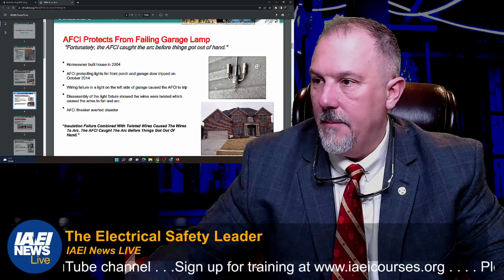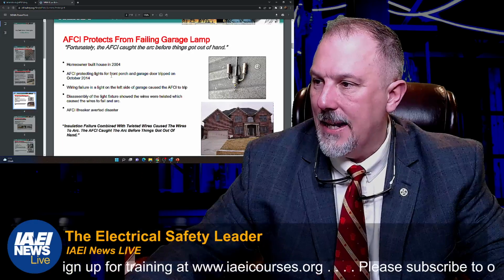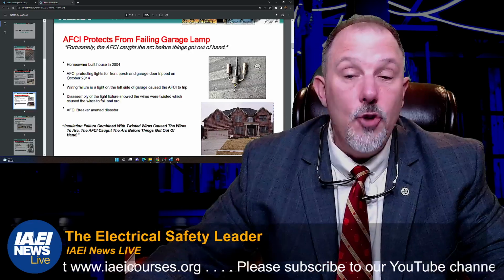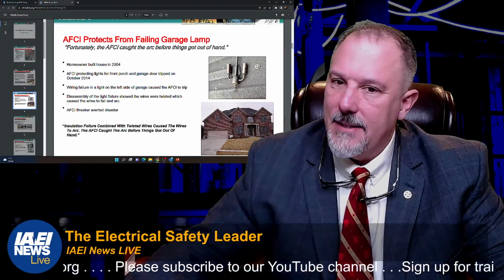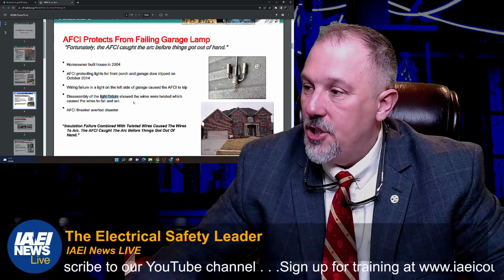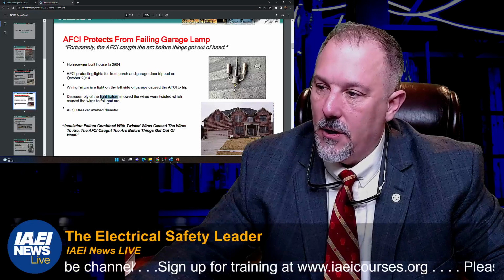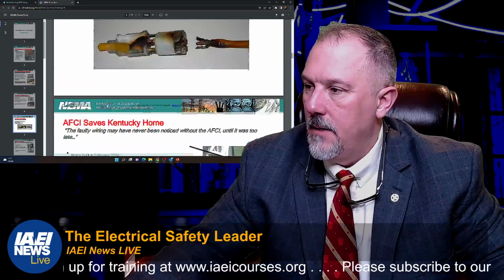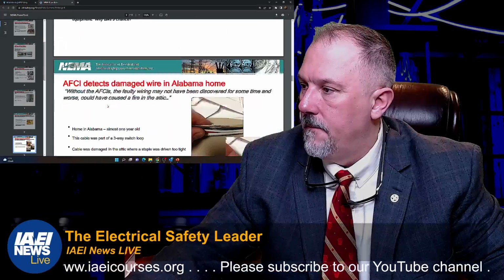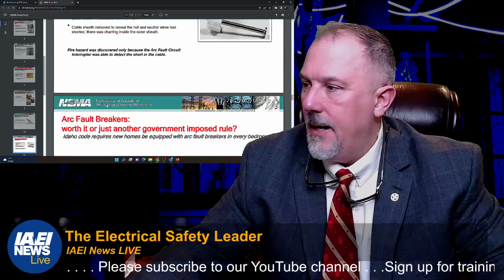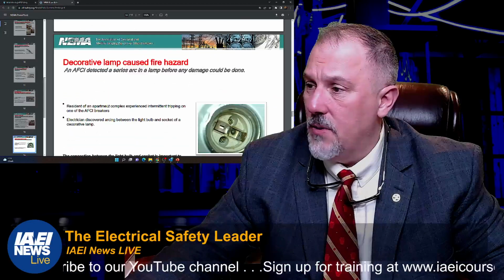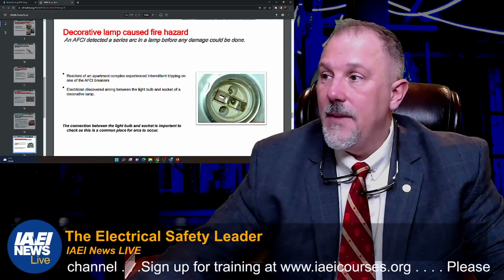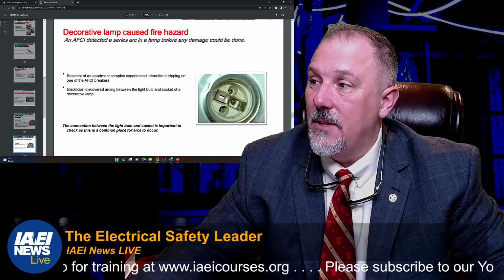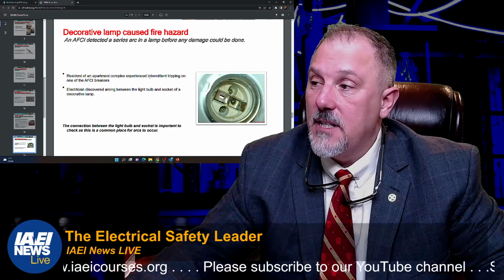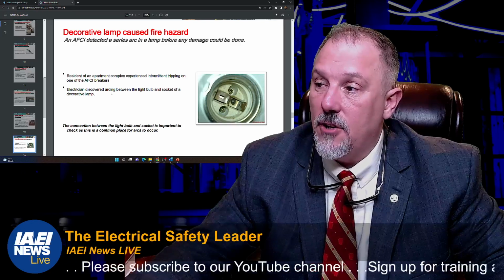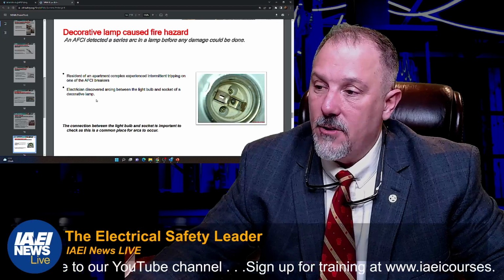Protects from failing garage lamp. Homeowner built house in 2004. AFCI protecting lights for front porch and luminaires. Disassembly of the light fixture, the luminaire, showed the wires were twisted, which caused the wires to fail and arc. AFCI breakers averted disaster. And this is all free and accessible to all of you as well. Look at this: decorative lamp caused fire hazard. An AFCI detected a series arc in a lamp before any damage could be done. A resident of an apartment complex experienced intermittent tripping on one of the AFCI breakers. The electrician discovered arcing between the light bulb and the socket of a decorative lamp.